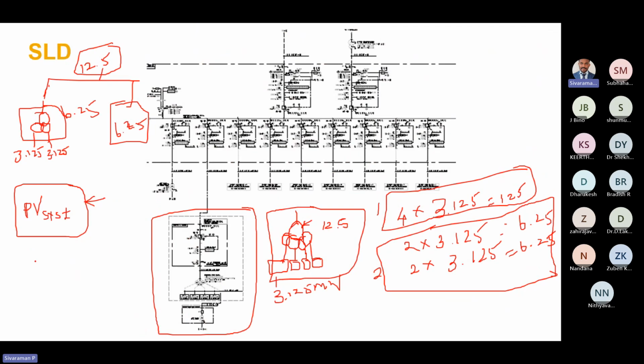It is the real power loss, so we can calculate it by means of I square R, where R is the total resistance and I is the current flowing through the cables. If we have this panel, one inverter, and so on, there will be n numbers like this. This will be cable connection one, and this will be n.